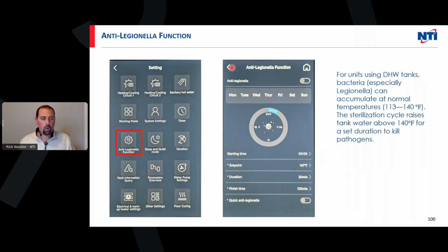So we do have, again, for domestic hot water, if we are using it, an anti-Legionella function in the machine where we have the ability to set a program. Typically when people are sleeping, we can turn this on and really raise that tank temperature above 140. This way we can kill any type of pathogen that may be in that water or growing inside that tank. In certain regions, I've been asking this question a little bit, I'm not sure everybody's code at this point, but in a lot of different areas we have to maintain tank temps over 140 degrees and mix it down with an external valve just for this one reason. If they don't have to do that, which seems to be common in a lot of other areas too, we have the ability to turn this mode on. So periodically we will run it to make sure that we're not having any of that Legionella going on.